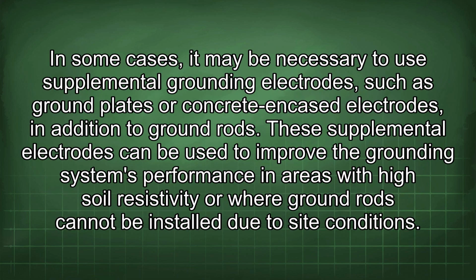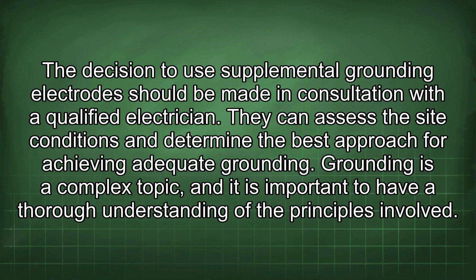In some cases, it may be necessary to use supplemental grounding electrodes, such as ground plates or concrete-encased electrodes, in addition to ground rods. These supplemental electrodes can be used to improve the grounding system's performance in areas with high soil resistivity or where ground rods cannot be installed due to site conditions. The decision to use supplemental grounding electrodes should be made in consultation with a qualified electrician. They can assess the site conditions and determine the best approach for achieving adequate grounding.